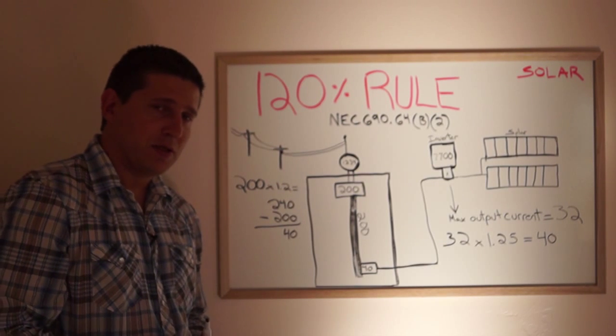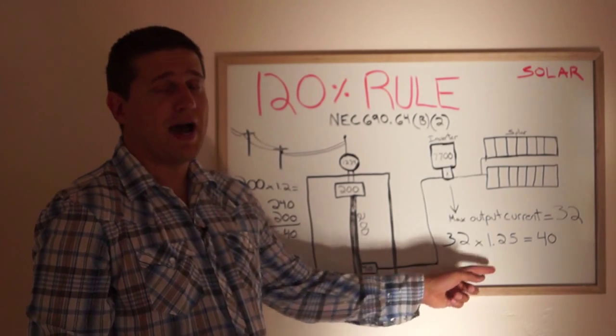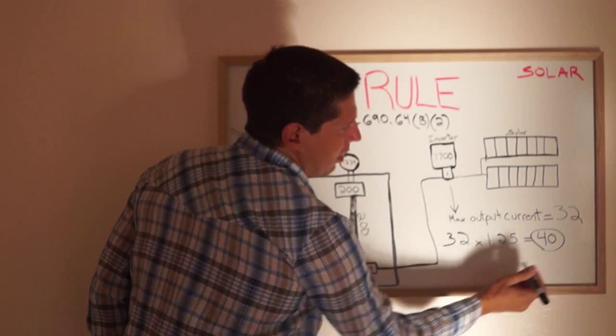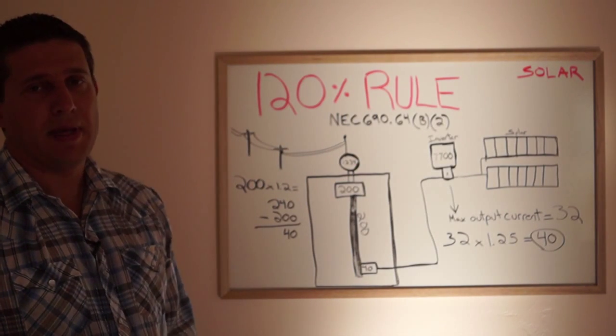Overcurrent protection still applies to solar. So we have 32 amps times 1.25 equals 40 amps. The largest system you can install on a 200 amp main service panel.